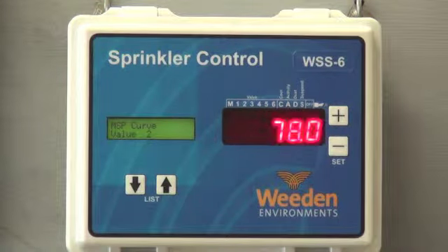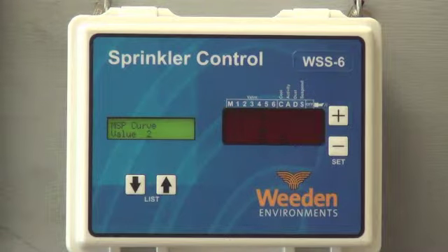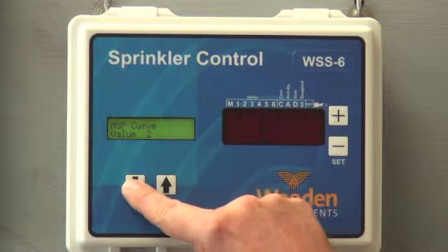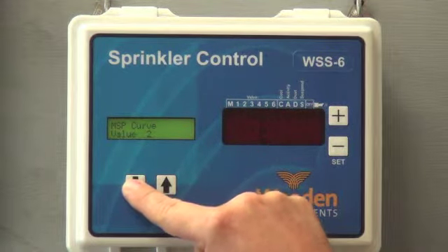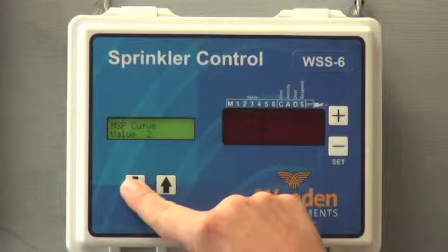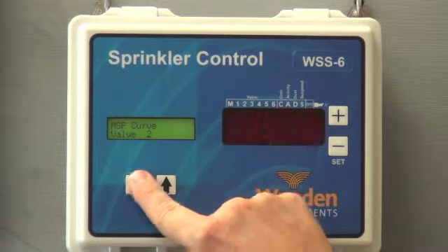So now we have our first set point at 28 days of age being 86 degrees, and the second set point being 56 days of age at 78 degrees. That set point is going to ramp down automatically from the age of 28 days to 56, bringing the set point down with the same 3 levels of cooling that we'd set up in the beginning. You'll see when I go down now, it's saying day 3 is 35.